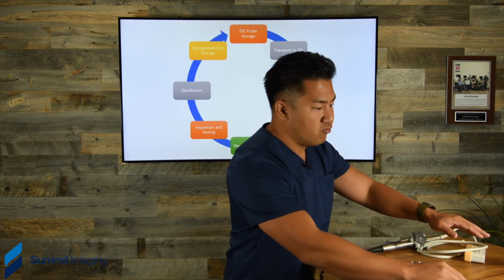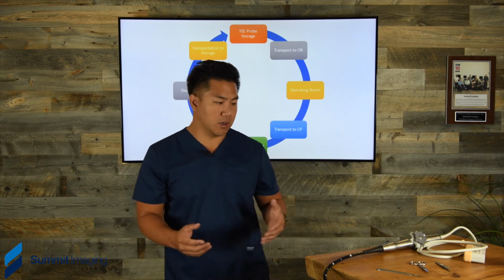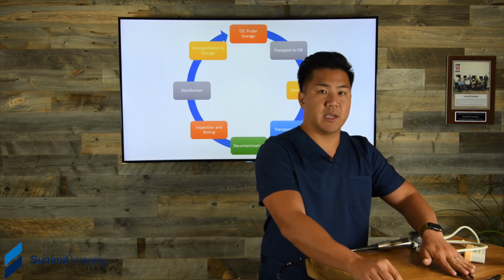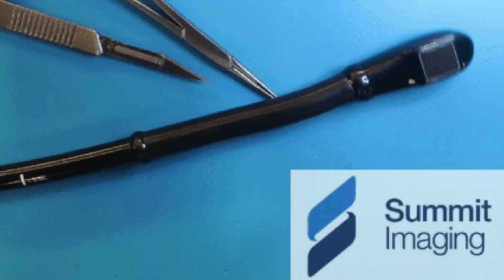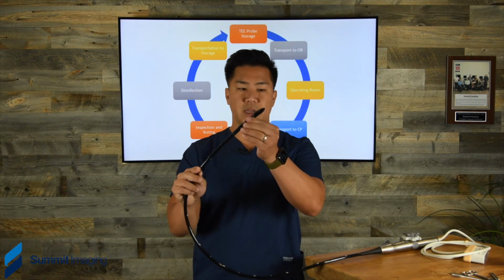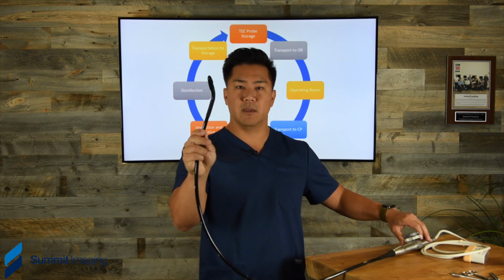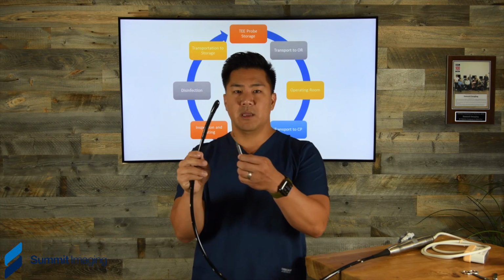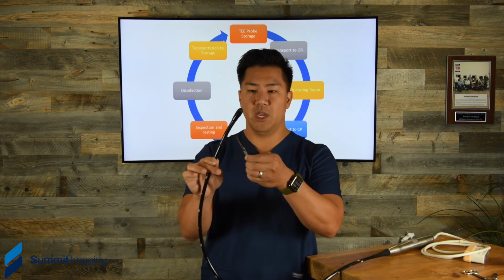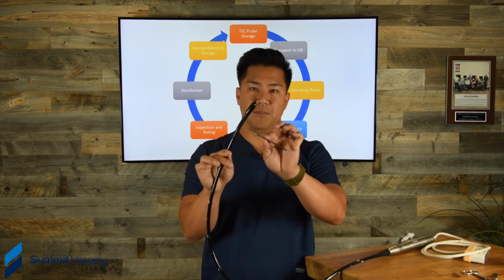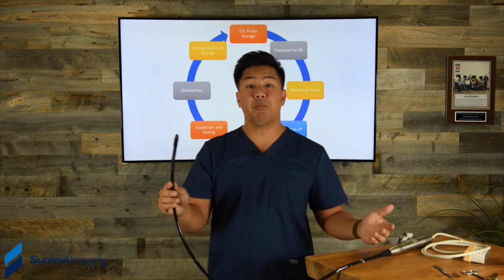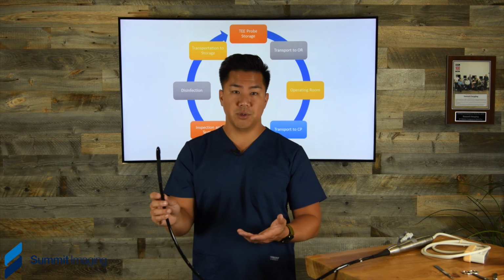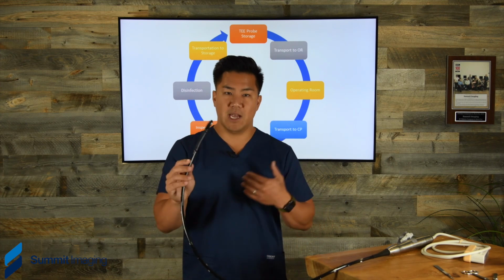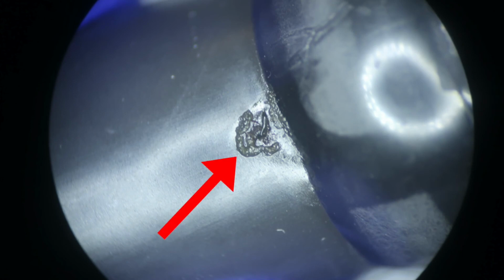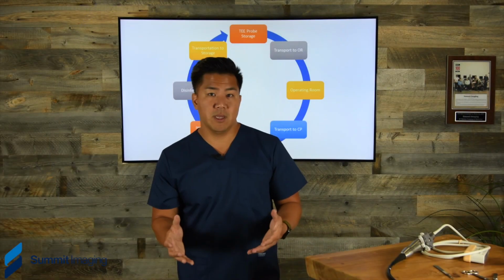And one thing is, when the technicians are prepping for a procedure, we've seen these sharp tools right next to the transducer on the table. Well, the construction of this TEE probe is a bending rubber that allows this transducer to articulate. And these sharp tools are very sharp to a degree where it will cause micropunctures into this bending rubber or even on the lens and compromise a transducer's not only performance, but also exposing the internals of that, where stomach acid might get in there, some disinfecting fluids might get inside the transducers, and ultimately will eventually, if not immediately, fail a leakage test and therefore need a repair.